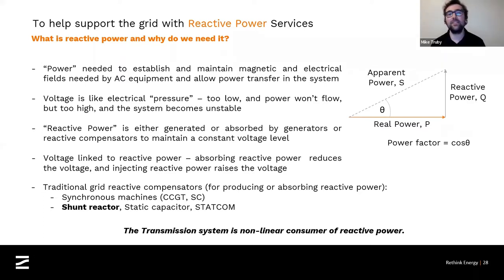And this is essentially the energy that we need to sacrifice in order to establish, maintain, and operate the electrical system. There's a lot of magnetic fields, electrical fields within that, in transformers, in generators, in motors, and even in the cables themselves. And we need this energy basically to be able to push power through the system. The analogy that people use a lot is the pint of beer. Beer is like the real power and the head is like the reactive power. The reason that you have that head on the beer is that you need that gas in the system to push pressure through the system and to make sure that the beer can flow.